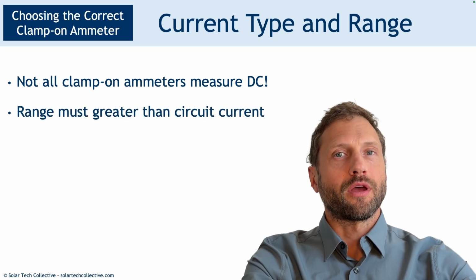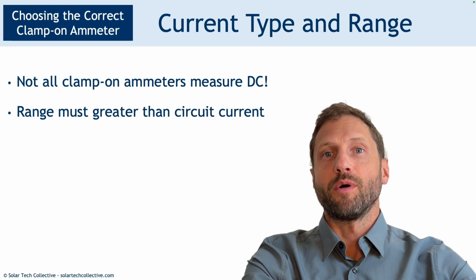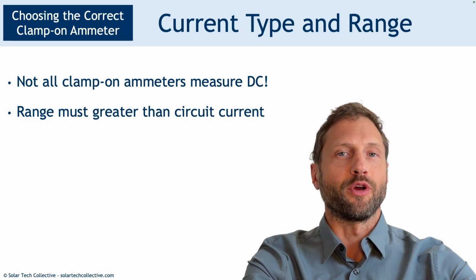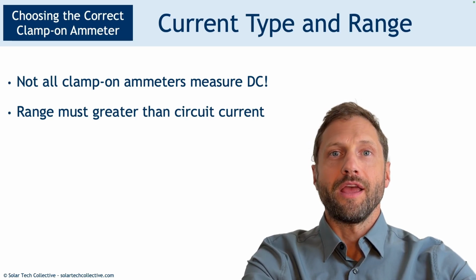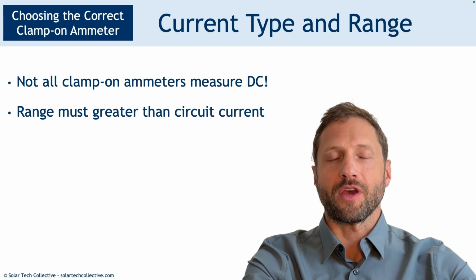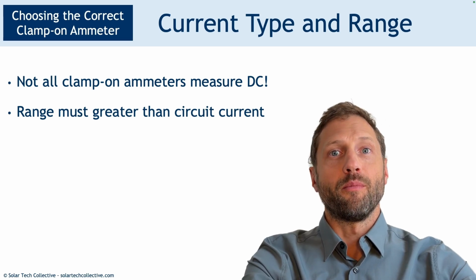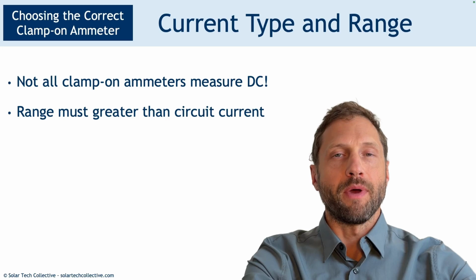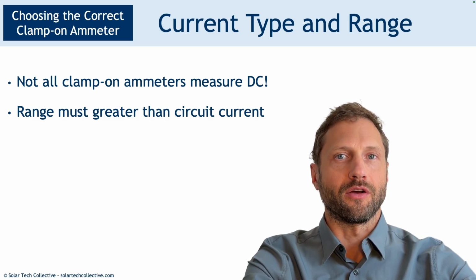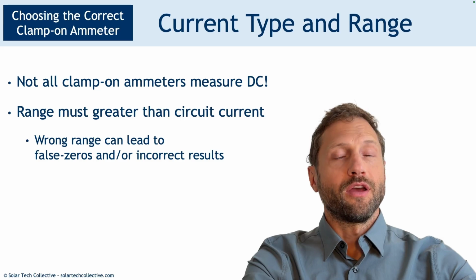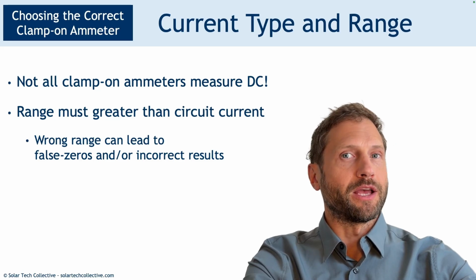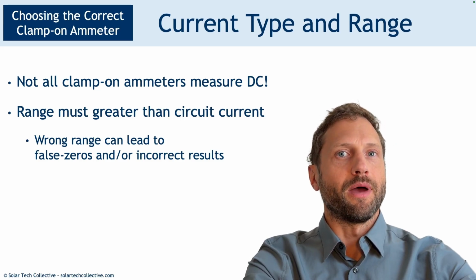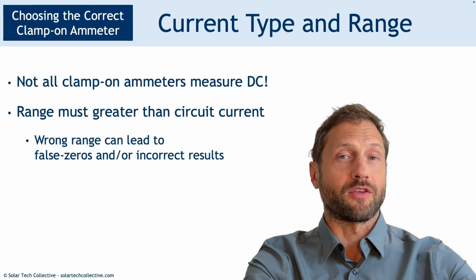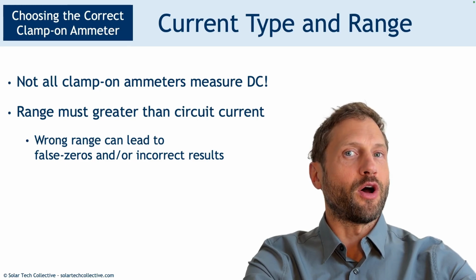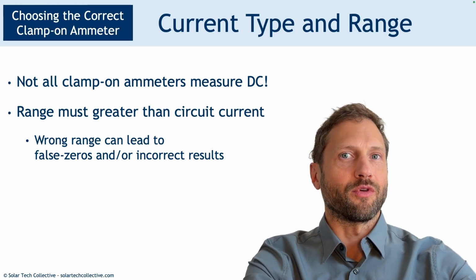The range for a multimeter is the minimum and maximum values that it can safely measure for a given setting. For current, it might be able to measure up to 400, 600, or 1000 amps, but the most important thing here is that its maximum value is greater than the maximum anticipated circuit current. Using the wrong range, for example selecting a meter that can only measure up to 400 amps, and trying to measure the current on a circuit that's carrying 650 amps can lead to false zeros and/or incorrect results.